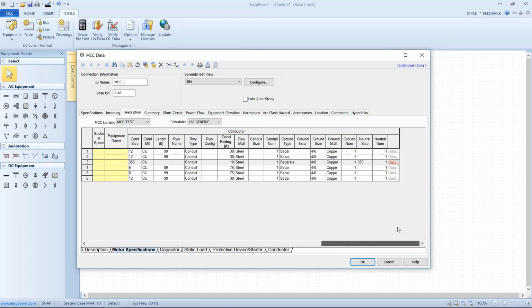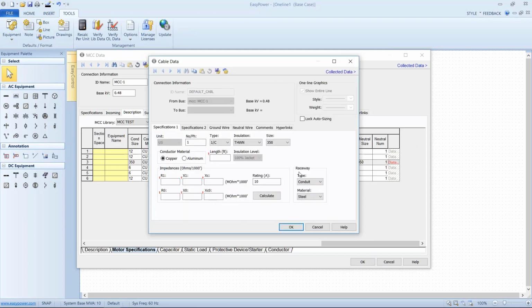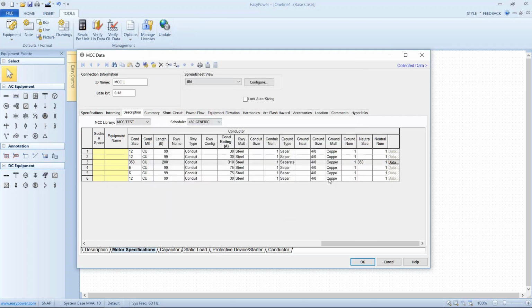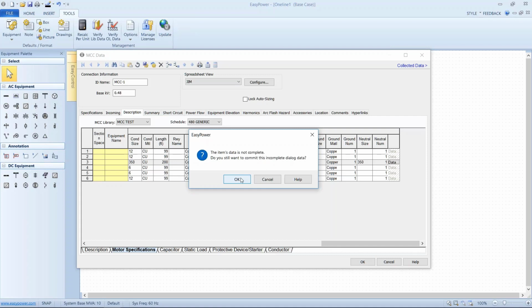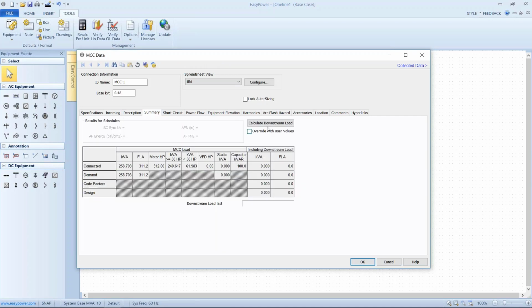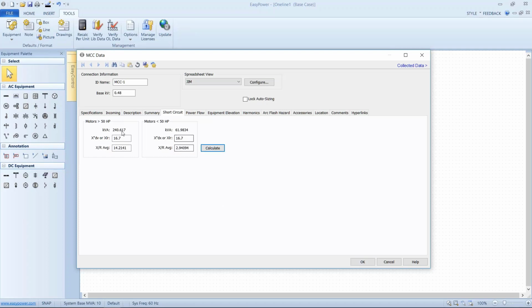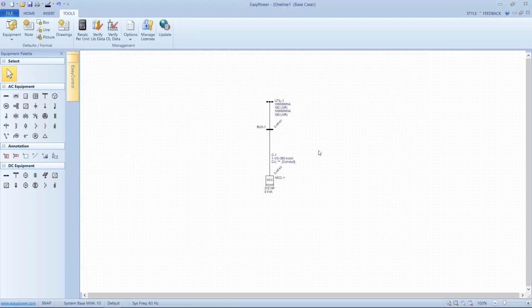And then finally, because this is all self-contained, I need to enter the parameters for the cable using the data dialog, a data entry. And again, this would be just like we would handle a standalone cable. All right, real briefly, once I've completed all the data entry, if I try to close at this point, it's going to tell me this isn't complete. Do you want to really close it? No, I don't. What I really want to do is calculate the downstream load and create an X over R calculation for this particular load, because again, this is going to be used at the bus level for the equipment duty. And so now that I've got that, I'm ready to rock and roll as far as coordination and analysis.